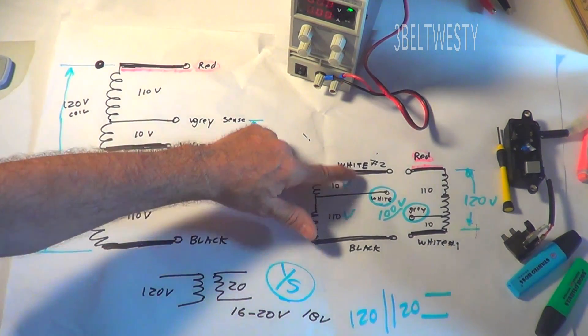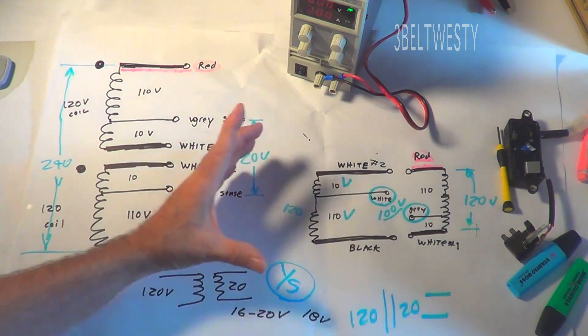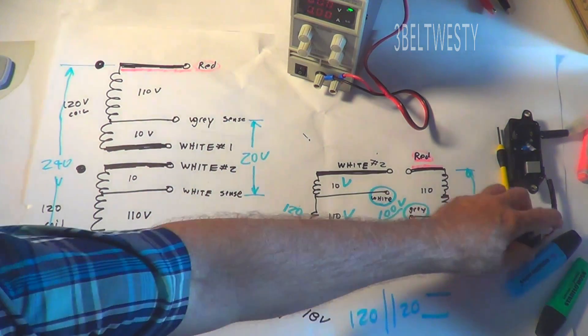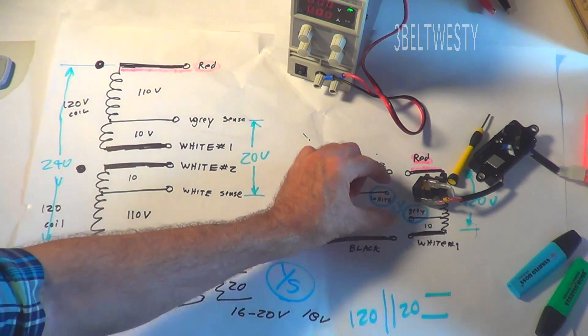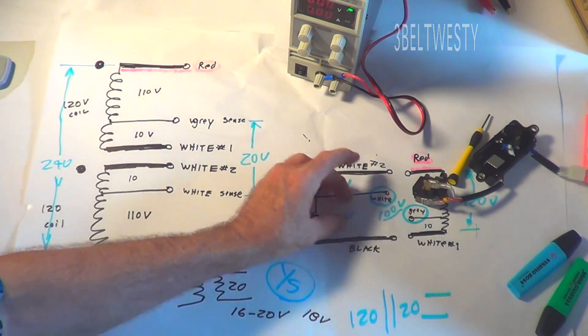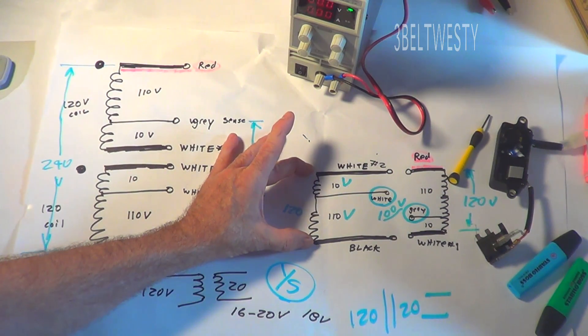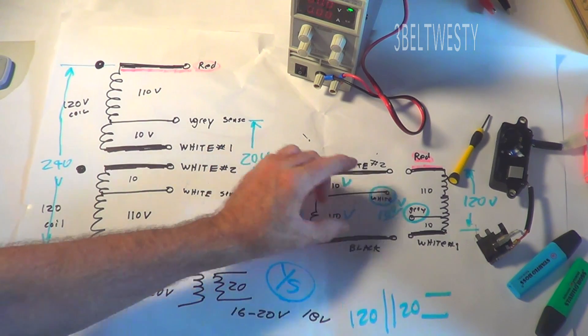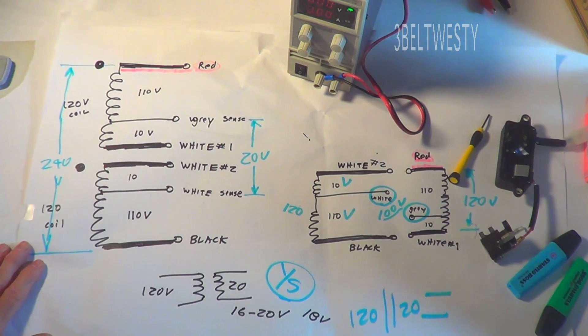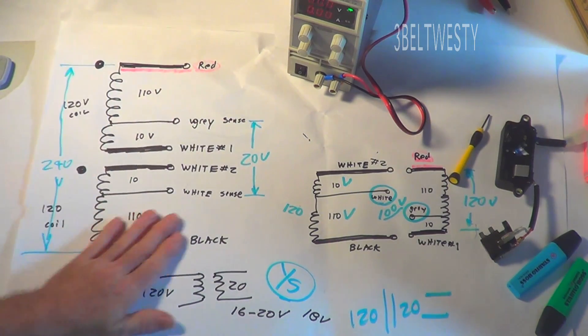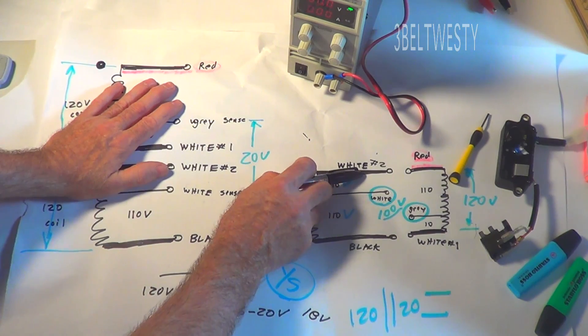When you wire it, the two coils in parallel, because they have this on either side of the tap, you're getting 100 volts here. So the AVR basically wants to make this, its goal in life is to make the sense voltage be 20. So it's going to drop the field current down, and that's why you only get 24 volts across this. So if 24 volts across here, this will be 20 here, and that's what the AVR was doing. So it has nothing to do that these two coils are in parallel, it has to do with the way this is now.